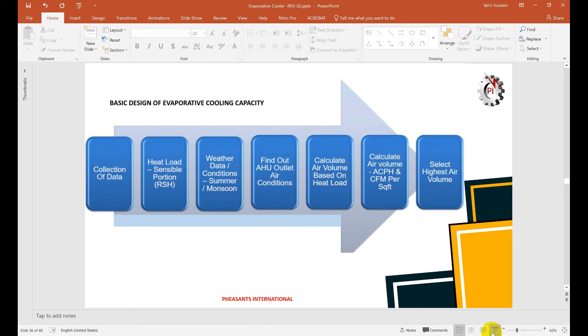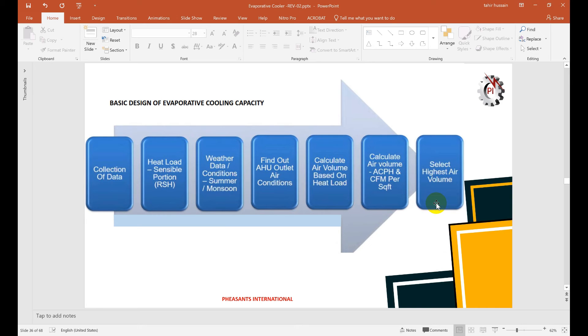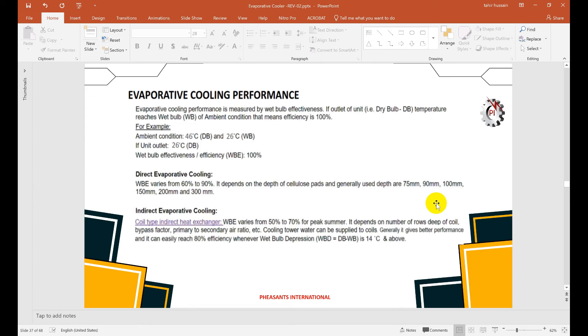Before starting the design, we must collect data: lighting load inside the building, number of occupants, building type, exposed surfaces. Then we perform heat load calculations — for evaporative cooling we need only the sensible heat load (room sensible heat). We also check weather conditions — dry bulb and wet bulb temperatures for summer or monsoon — then determine AHU and outside air conditions, calculate air volume, air changes per hour, and CFM per square foot. The higher result from heat load, air change, or CFM per square foot calculations governs the design.